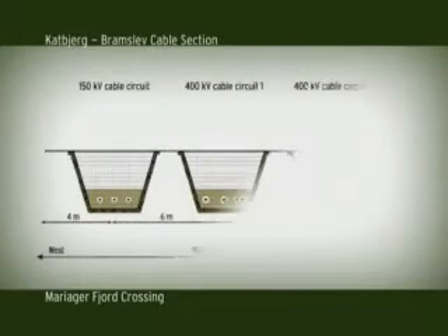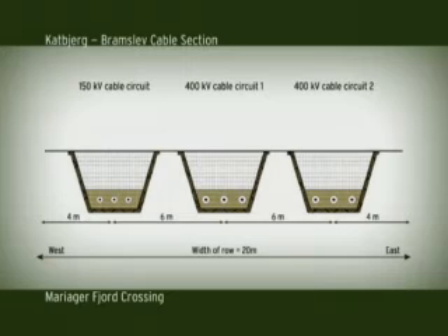The cables lie in a flat configuration. On land, the phase spacing is 300 mm, while under the inlet it is 1 metre. The spacing between the 2 400 kV circuits is 6 metres. The spacing between a 400 kV circuit and a 150 kV circuit laid in parallel is also 6 metres.